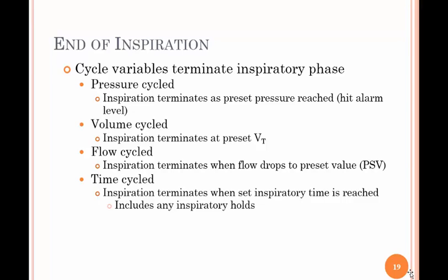Cycle variables cause the end of inspiration — terminating the inspiration is referred to as cycling. Pressure cycled: inspiration terminates as a preset pressure is reached, which may be the pressure limit alarm. Volume cycling: inspiration terminates at a preset tidal volume. Flow cycled: inspiration terminates when the flow drops to a preset value. Time cycled: inspiration terminates when the set inspiratory time is reached, including any inspiratory holds. So cycling mechanisms are pressure, volume, flow, and time.